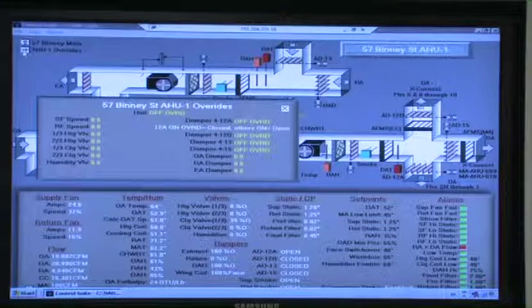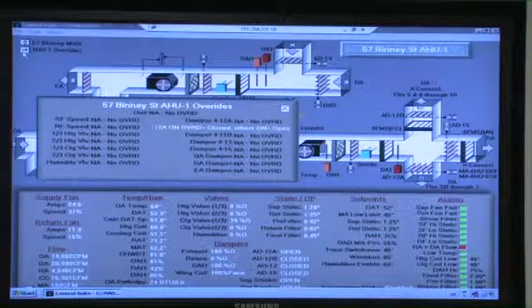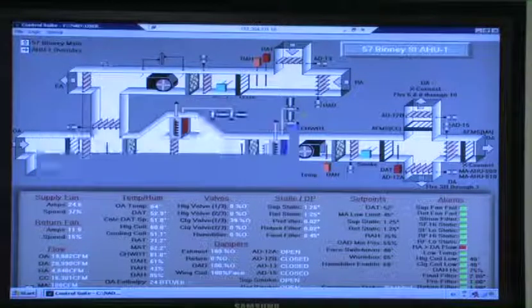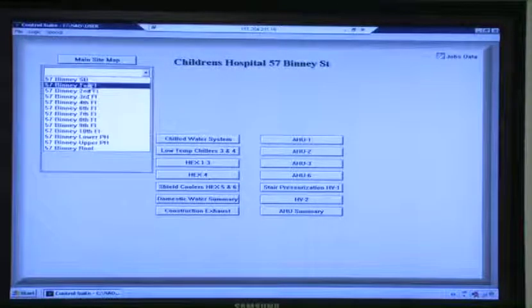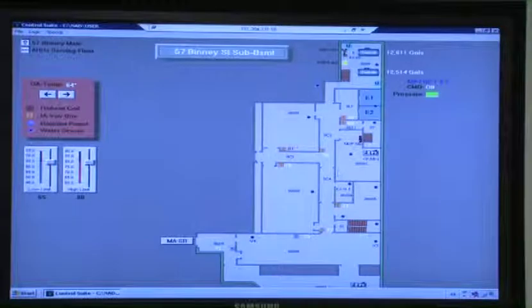And the overrides. We'll go through air handlers in a minute. Okay, so if we're all set there, unless there are any questions on that, or you see something missing and you think it'd be better. What do we got flashing up there, Steve, by the tanks? Because the fuel oil system's offline. That's the fuel oil pump system. It's offline right now because we're feeding off the other system. Until we put that online officially and divorce off the other ones, that'll stay all on.